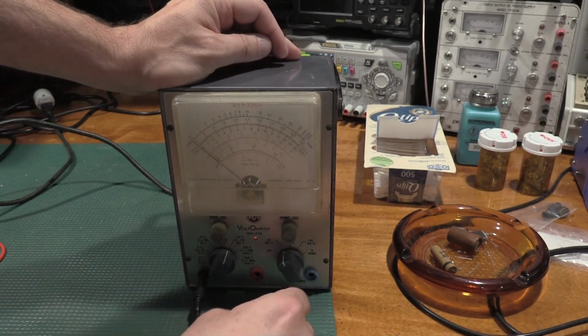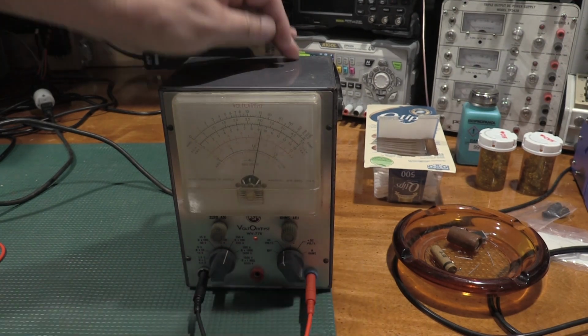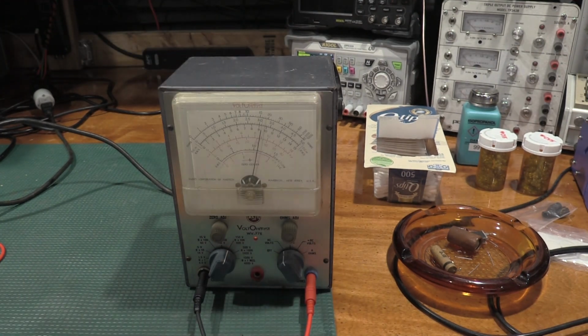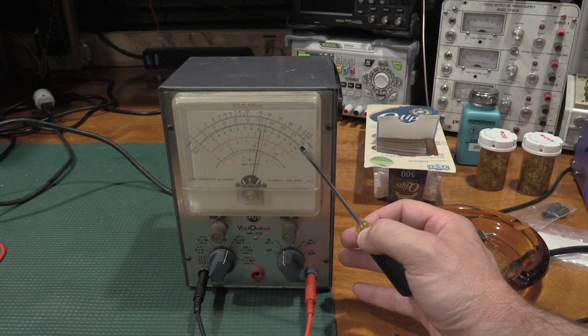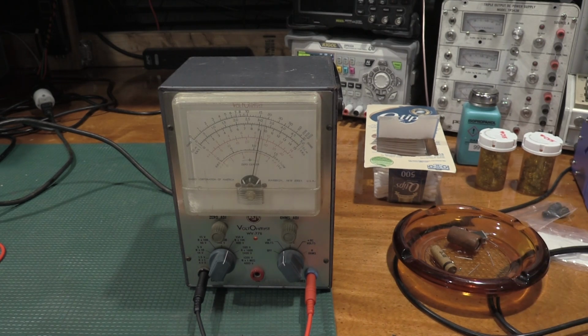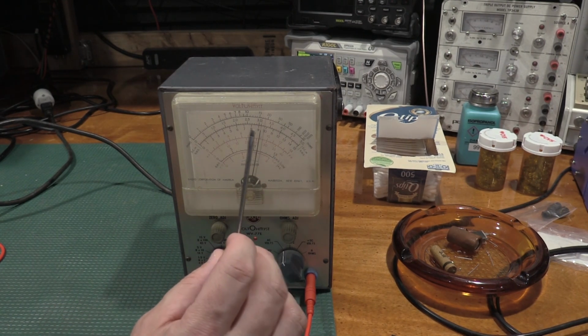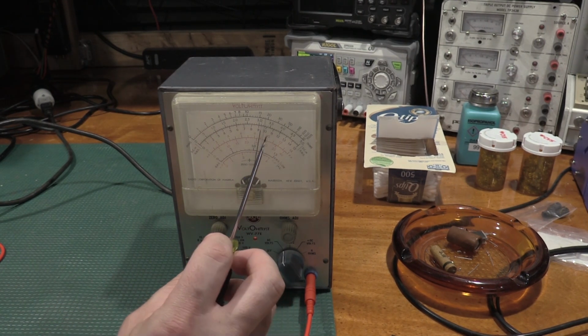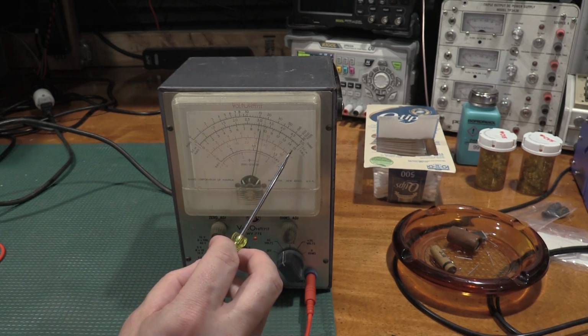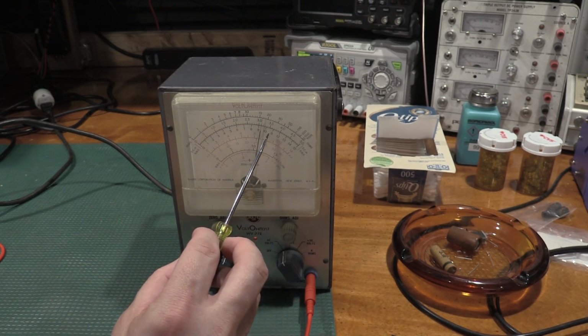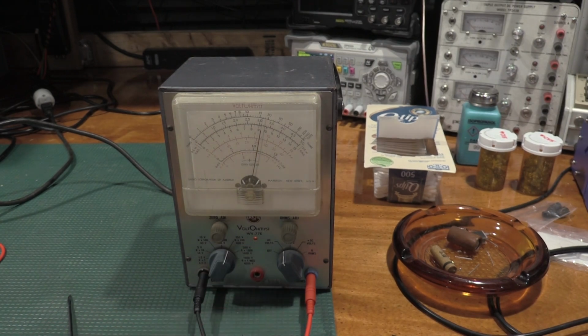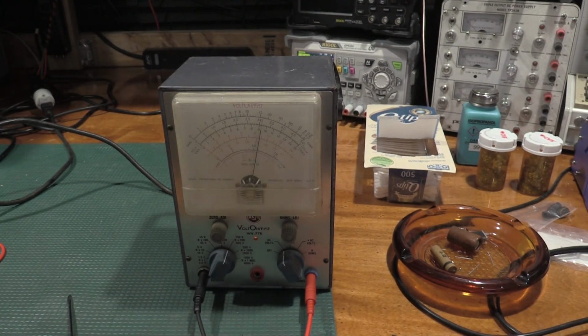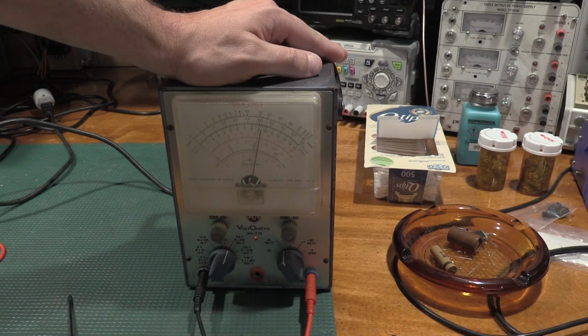Not going to short anything out at 60 hertz. So for the 150 volt setting, we need to read from scale B, which is this one. And I need to set for 115. But to get a more accurate reading, because this would be 150, I want to drop it back to 110, so we'll be right here. So I'm going to reset this up, test it for 110, and we'll do the adjustment on that setting.